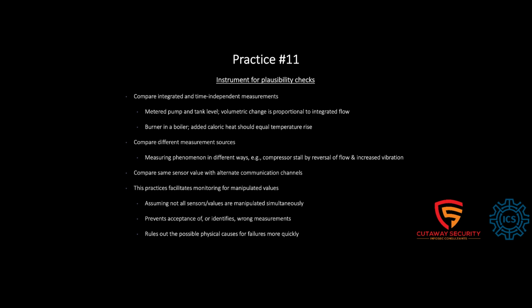But then other times, maybe you don't have two different sensors or two different types of sensors, but maybe you can look at the same sensor value via alternate communication channels. So maybe there's a backplane communication and a 4 to 20 milliamps, or some kind of alternate path, so that you can measure the same thing using two different ways. That way, if the attacker manipulated one value in one location, but not the other, you get an alert that someone is trying to play with these values. And again, like I mentioned, this assumes that not all sensors and values are manipulated simultaneously. But if you follow this practice, at the very least, it identifies wrong measurements.